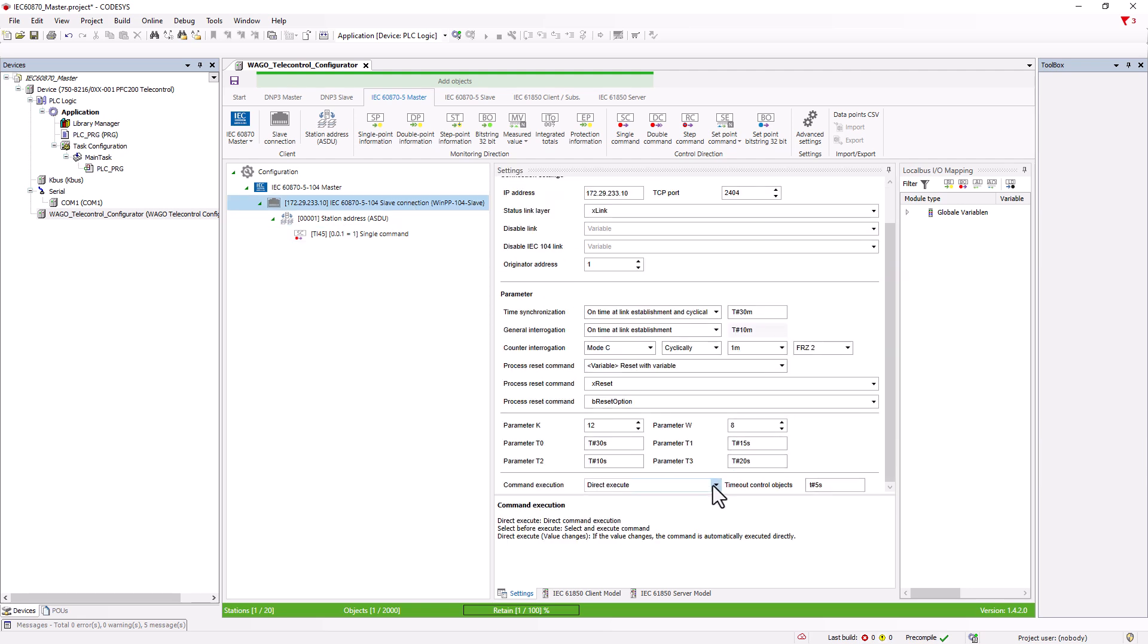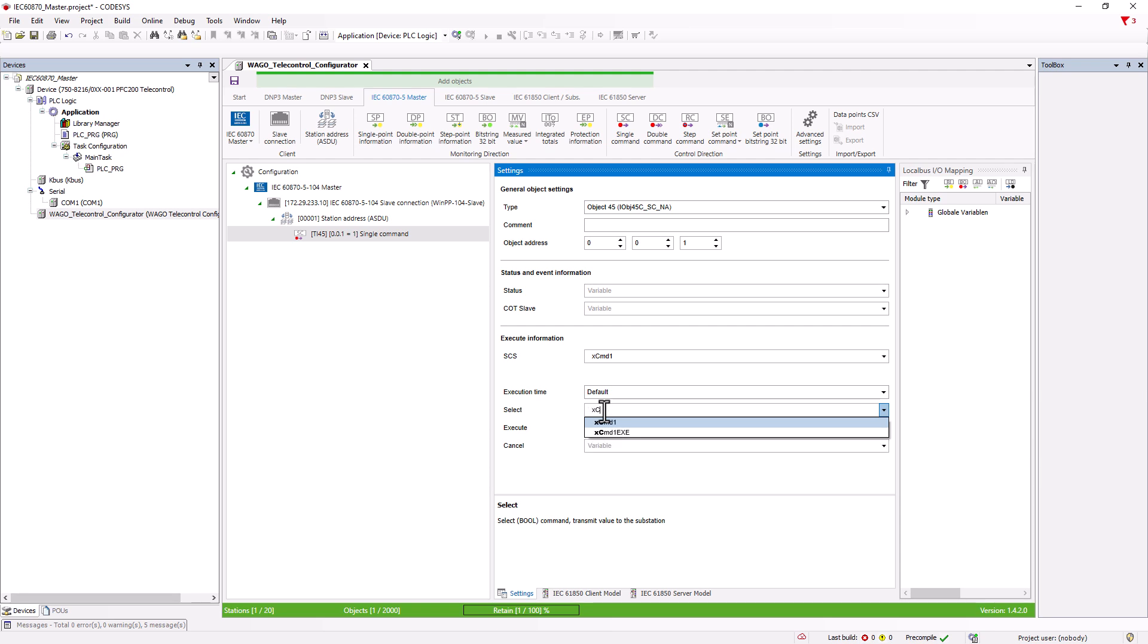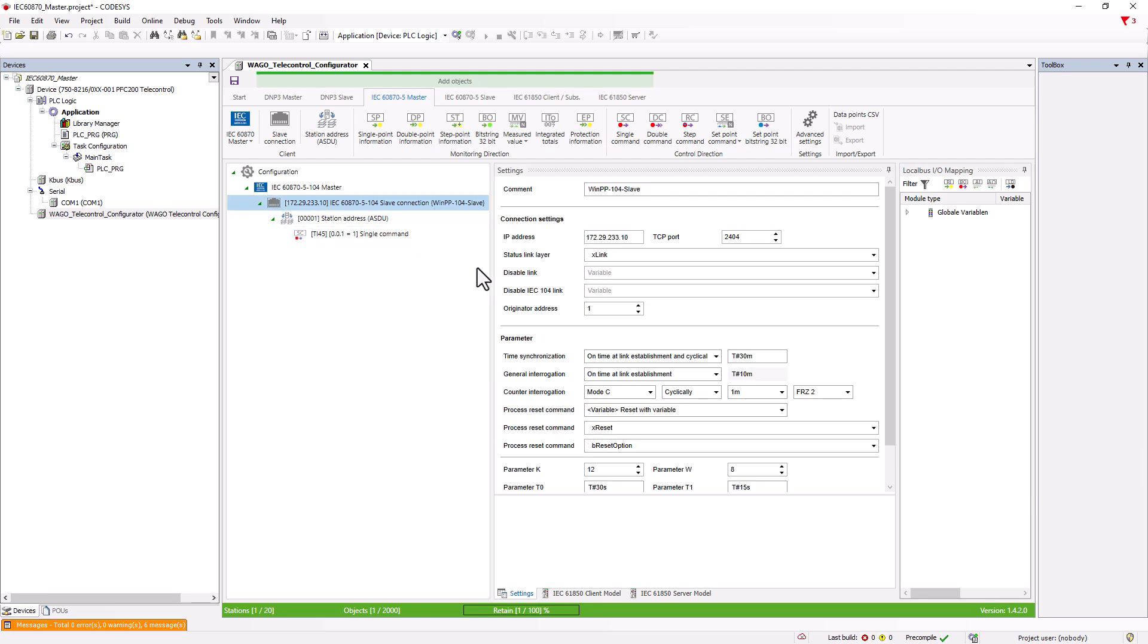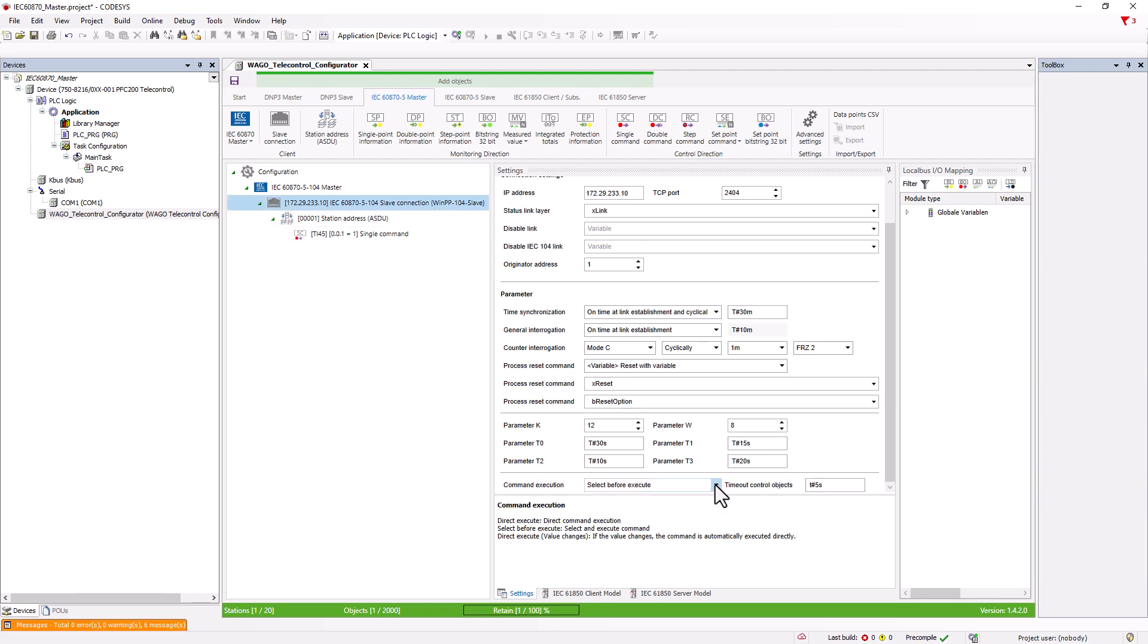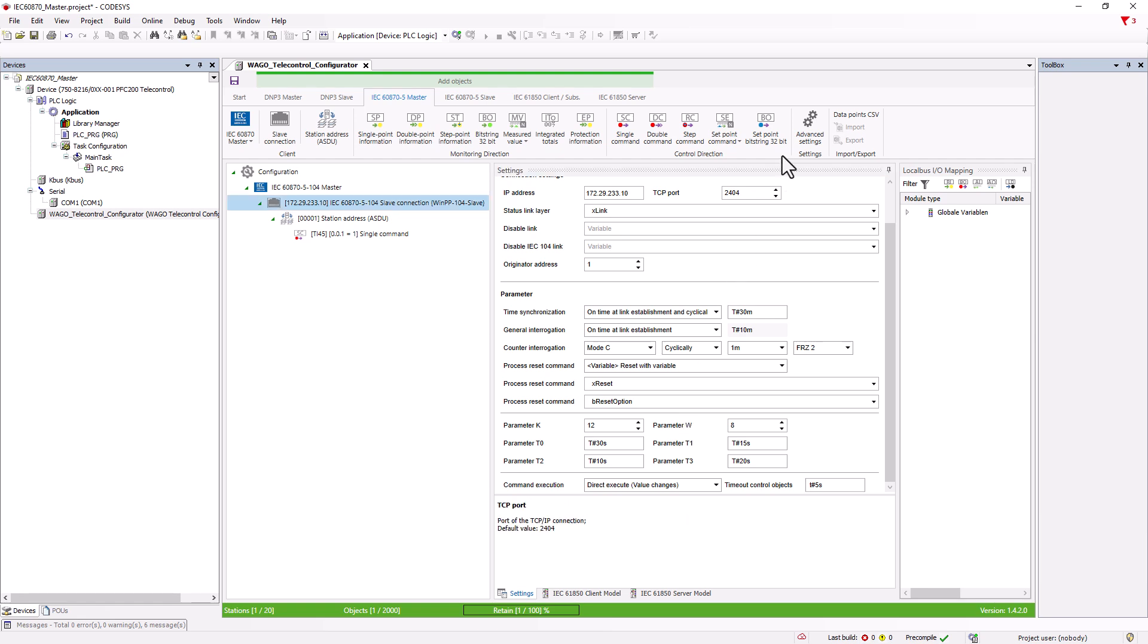If we now switch to the select and execute option, we can also specify the variable for the preselection, for which we also need the positive edge. In gateway applications where commands are passed from the slave side to the master side, it is therefore always necessary to ensure that the positive edge is also present. As this can involve a considerable amount of programming, there is the option of direct execution on value change, in which case variables can simply be mapped from the slave to the master in order to pass them through directly. This is explained in more detail in the video Gateway applications in telecontrol.